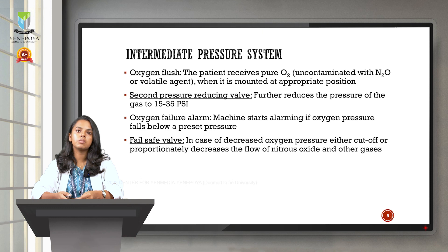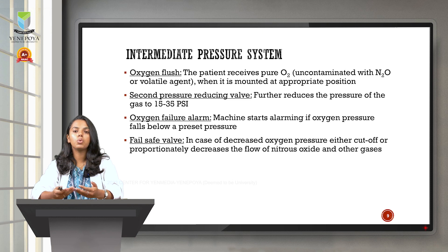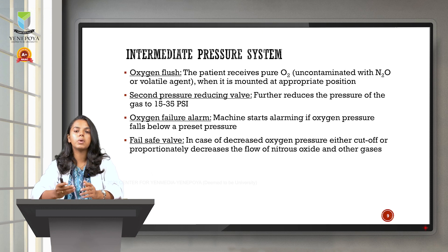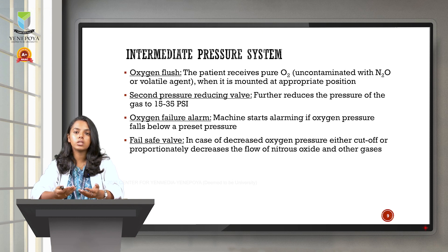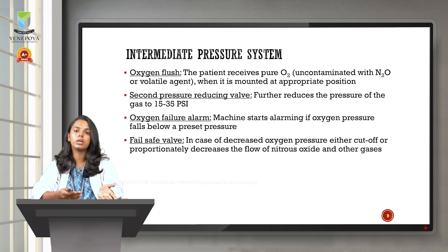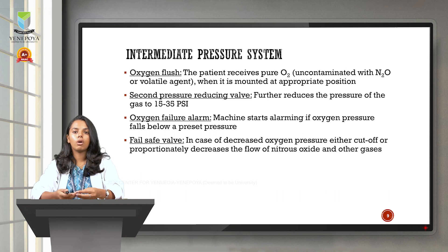The third component of the intermediate pressure system is the oxygen failure alarm, which starts beeping when the oxygen pressure inside the machine falls below a preset level. The fourth component is the fail-safe valve — in cases of decreased oxygen pressure, the fail-safe valve either cuts off or reduces the pressure of other gases inside the machine, so that we do not administer a toxic hypoxic mixture of gases to the patient.